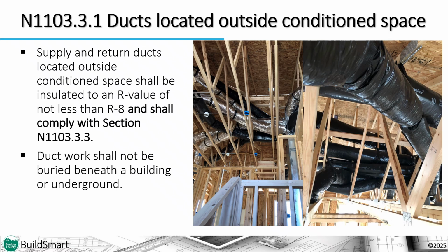Supply and return ductwork located outside conditioned space shall be insulated to an R value of not less than R8 and shall comply with Section N1103.3.3. Ductwork shall not be buried beneath a building or underground at all. So although the air handling unit cannot be installed in an attic, the duct can still be located in the attic if it is insulated to at least an R8.